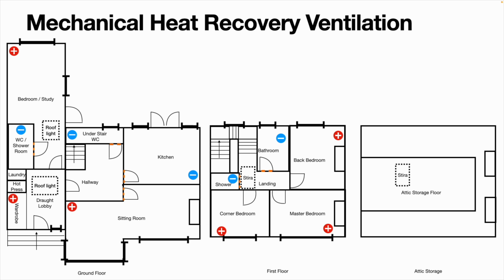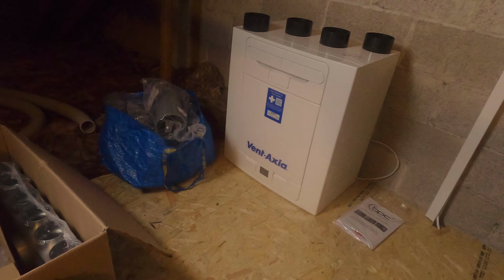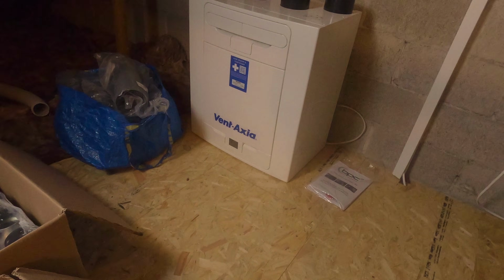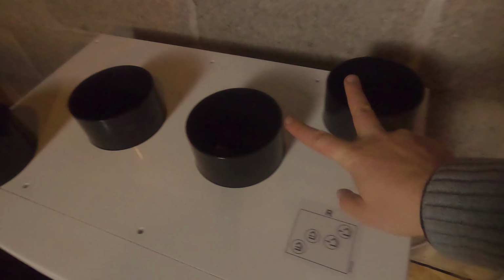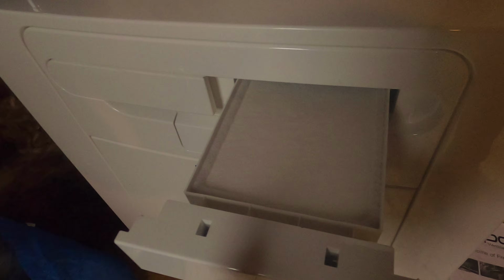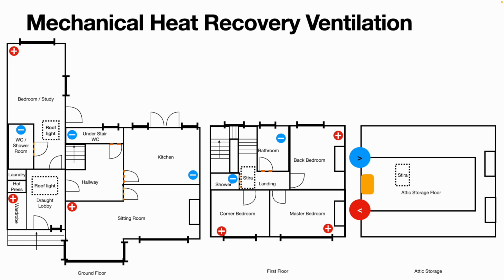The next thing to contemplate is where to site your heat recovery ventilation unit. It's a big bulky unit, maybe 800 mil wide by a metre high by a couple hundred mil deep, depending on the size you need. In my case, not ideally, I've sited it in the attic. Typically you want it in a conditioned, room-temperature space, so you're not leaking heat.